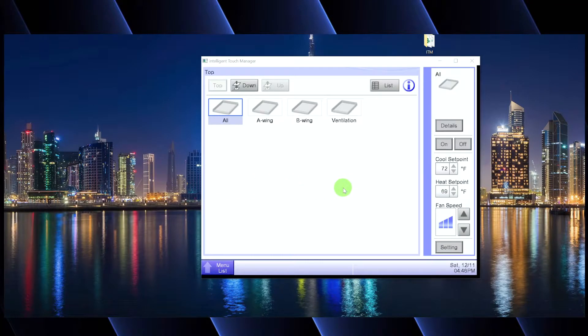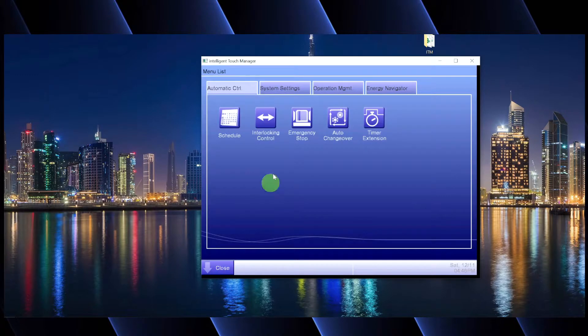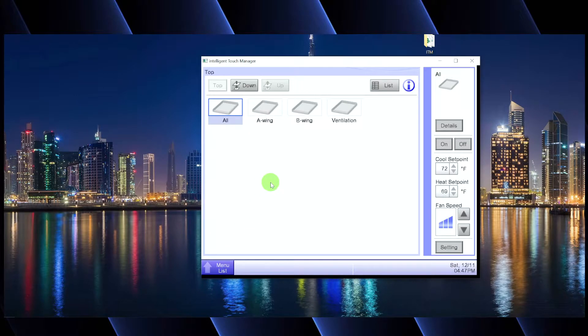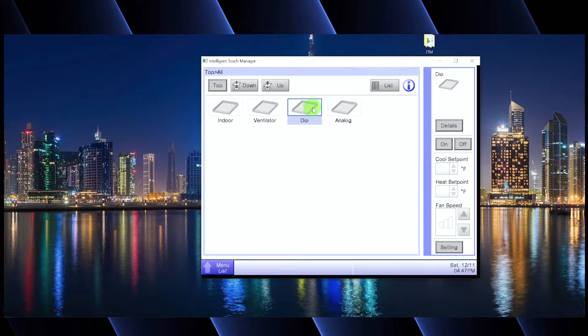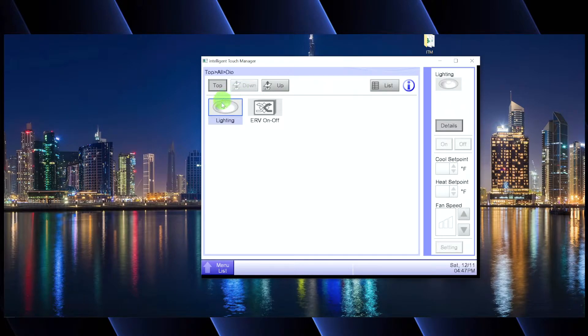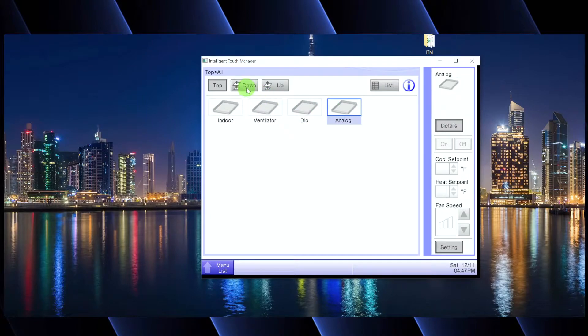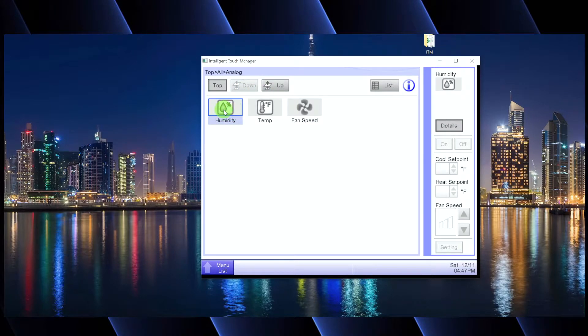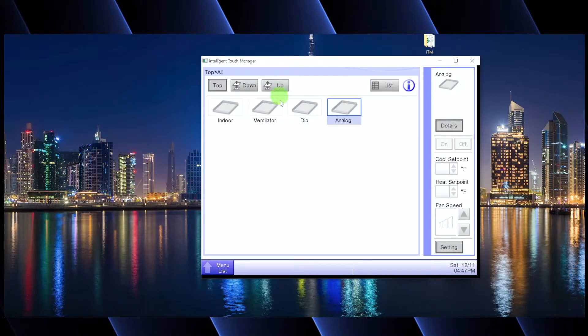So we're going to go back to the desktop like we've been doing, and we're going to be playing around with something in the menu called interlocks. Before we do, I want to do a quick brush-up on what we talked about in the last video. We created digital inputs and outputs and analog inputs and outputs — basically five points: a lighting input, an ERV on/off command output, an analog input for humidity, an input for a temperature thermistor, and an output going to a fan. So we have some things we can now control that aren't necessarily part of the Daikin system.